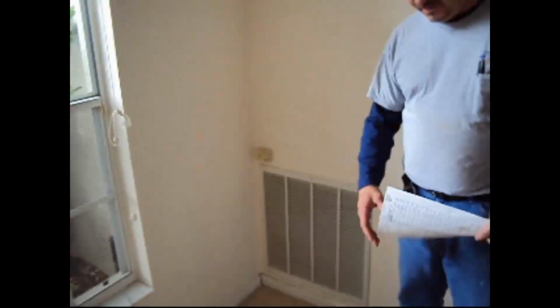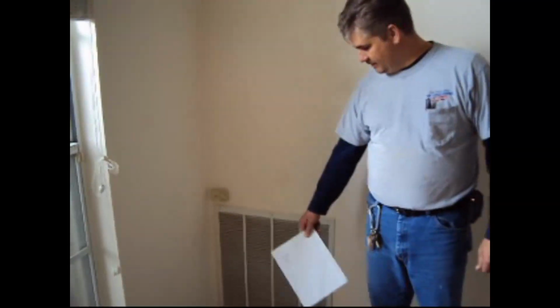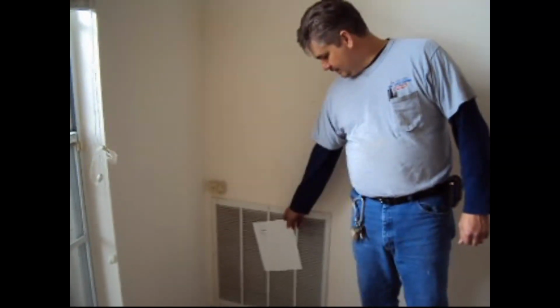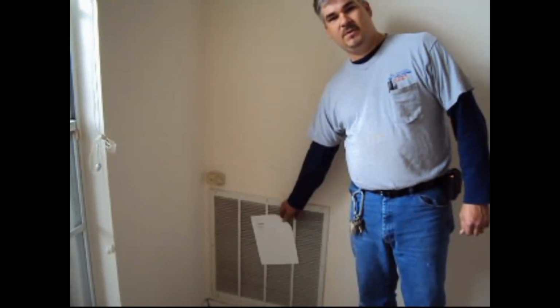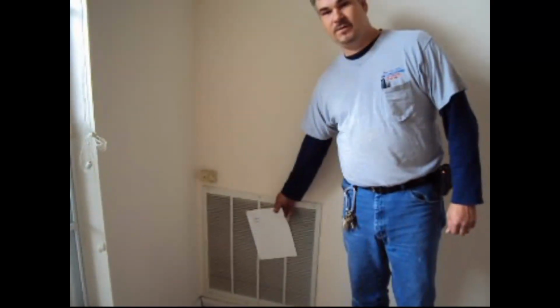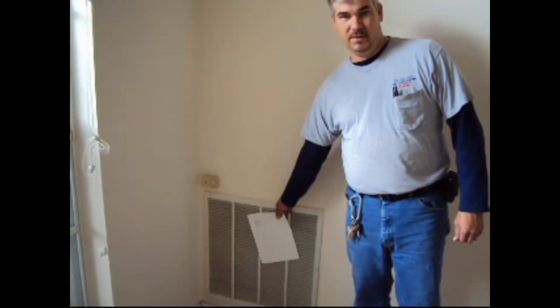And I'm just going to use this piece of paper to demonstrate that the machine is running. The grill just sucks up that piece of paper and holds it right there. That means the indoor unit is running and it's pulling air through the indoor unit. Now we're going to go outside to the outdoor unit and make sure it's running.